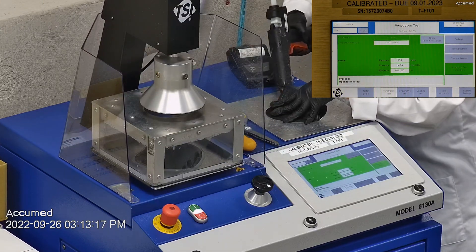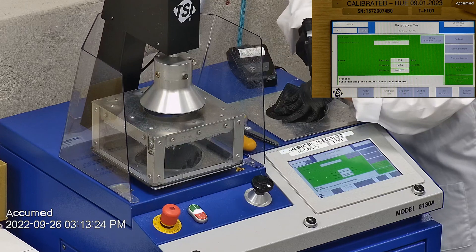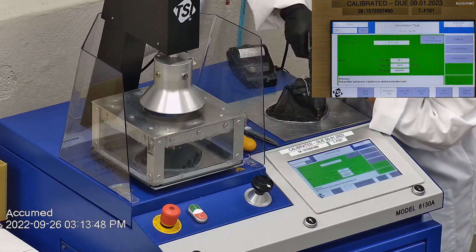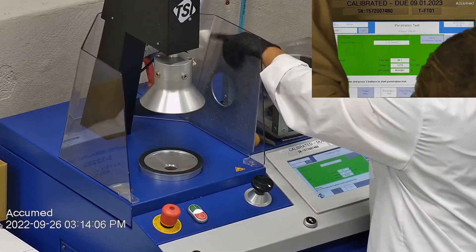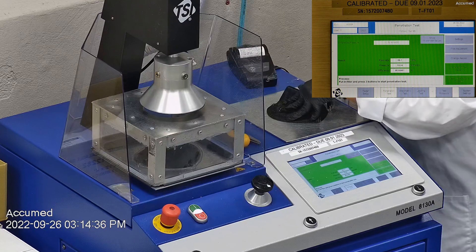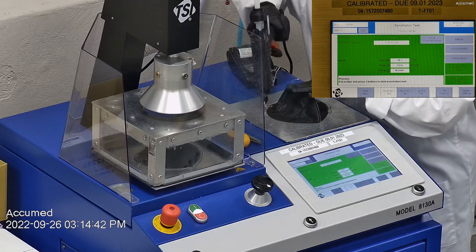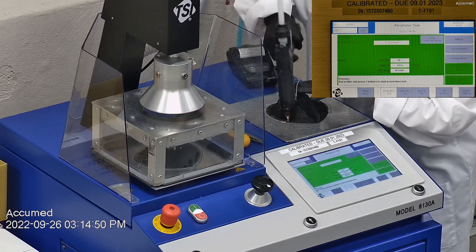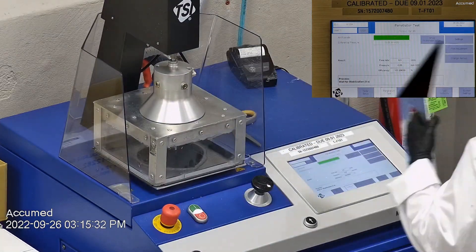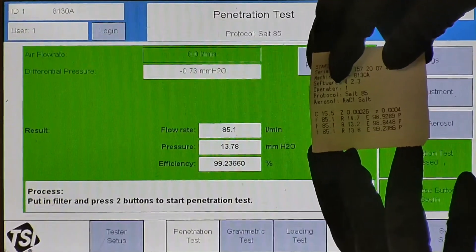The first sample had a filtration efficiency of 98.92% and a pressure drop of 14.7 millimeters of water. The second sample had a filtration efficiency of 98.84% and a pressure drop of 13.2 millimeters of water. The third sample had a filtration efficiency of 99.23% and a pressure drop of 13.8 millimeters of water.